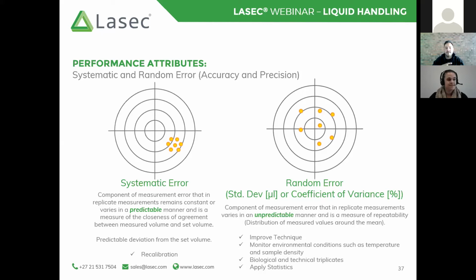If we look at the systematic error on the left-hand side, we can see that this is quite a predictable change in or deviation from what our set value is. We can assume that our set value is the center of this bullseye chart, and that is what we have set the pipette to. That's what we expect to aspirate and dispense with each pipetting step. However, based on our results, we can see that those measurements deviate by a certain amount each time. You can notice that this deviation is quite precise, in terms of the measurements being quite close to each other. As an example, if I had set my pipette to 1,000 microliters, I could be getting 999, 998, 997 continuously. They are quite closely grouped, but I would know that that is not the volume that I had set. So it is precise, but it is not accurate. It is not what I wanted to pipette.